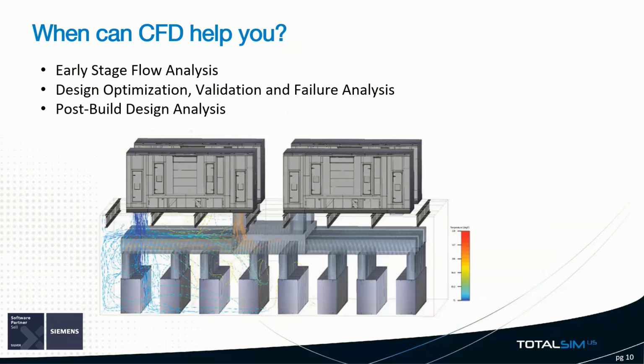There isn't a right or wrong time to incorporate CFD into your design workflow. In early stages, we can use CFD to look at basic airflow around a room, so you can use that information to best place your equipment and cooling systems. Design optimization validation is often the most popular time to use CFD. This is when you have an initial design and want to see how it performs. It could be a perfect design, or optimization is needed to mitigate undercooled or overcooled regions. This could be several iterations.